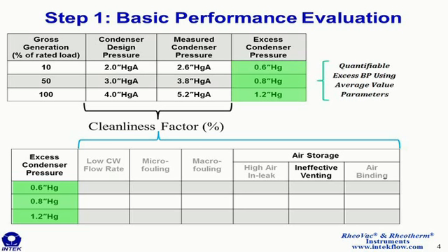For example, if you're venting two separate shells and the design shows that 50% of the capacity should be on each shell, well, if one shell has 80% and the other shell has 20% venting capacity, then that can cause air storage. So all of those mechanisms are wrapped in the ineffective venting column, and they can cause air storage and high condenser pressure. The last category is air binding, and whole condensers have had modular replacements because of this issue. These are bundles and air removal sections that were poorly designed to begin with and allow pockets of air to exist at all operating conditions. It doesn't matter how high the vacuum equipment capacity is or how low the air in-leakage is, these pockets persist and cause excess condenser pressure for all operating conditions.